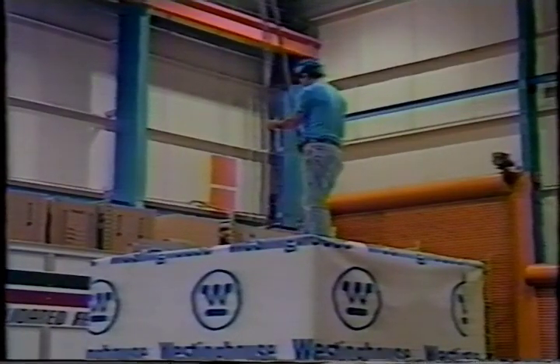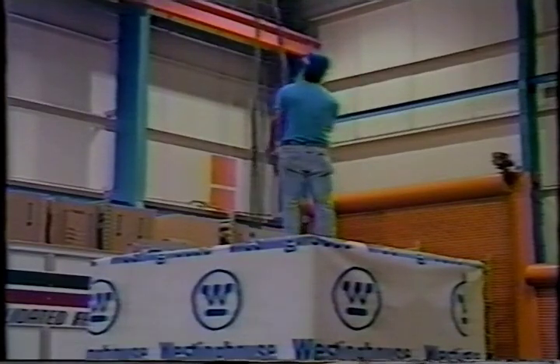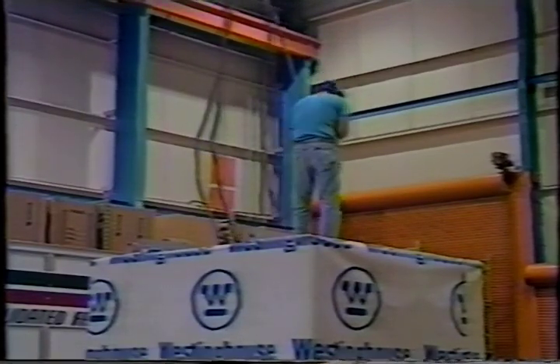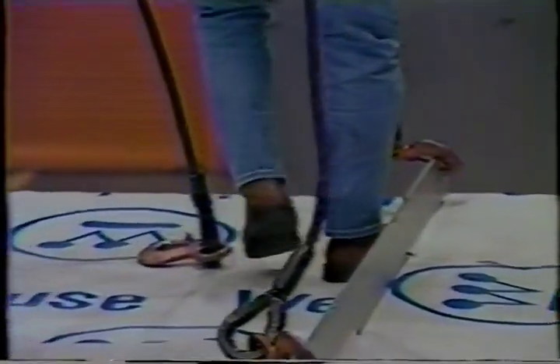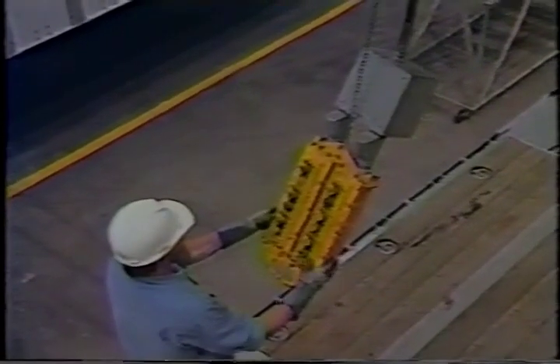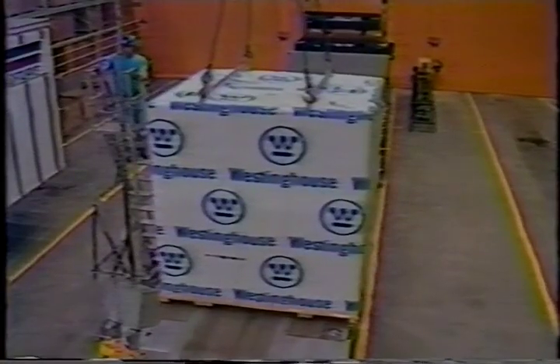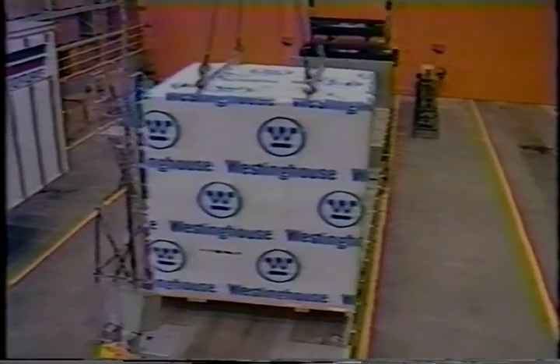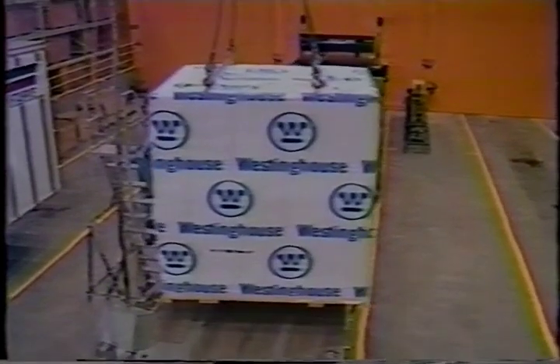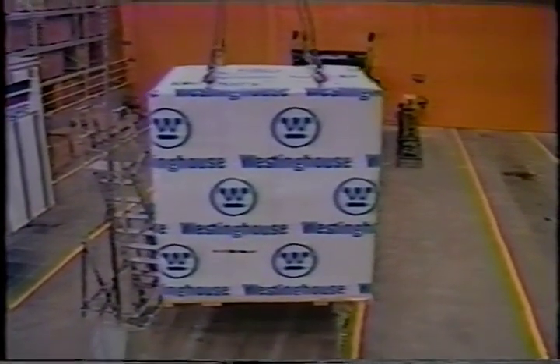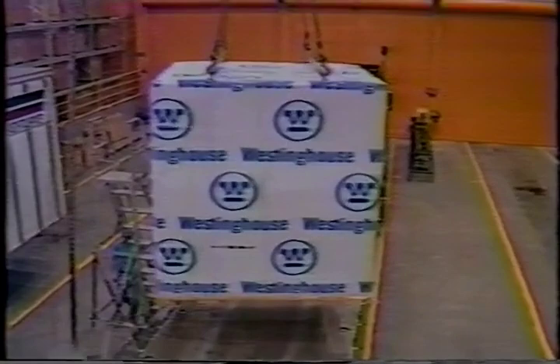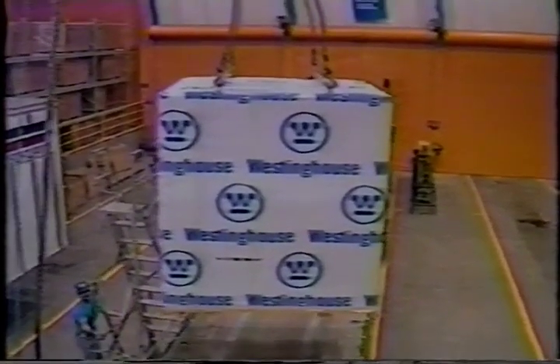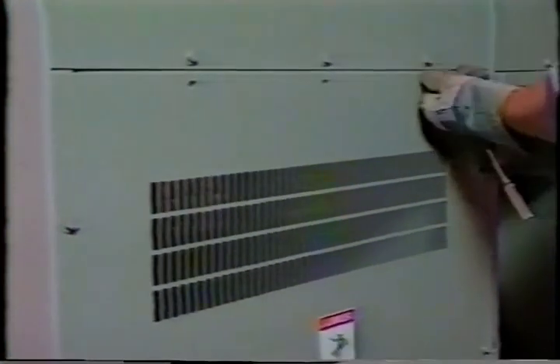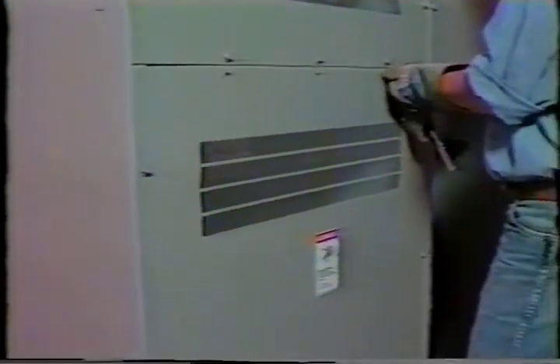The preferred method of moving metal-clad switchgear is by overhead crane. Lifting members are bolted to the top of each shipping group for this purpose. Once the shipping group is located at its final installation position, the lifting members may be unbolted and discarded. If a crane is not available, the equipment is designed with the provision for attaching jacking plates in order to raise the units for the positioning of rollers under the shipping group.